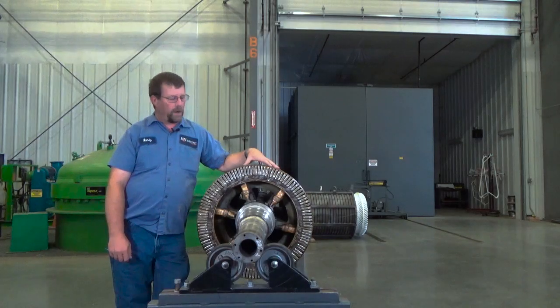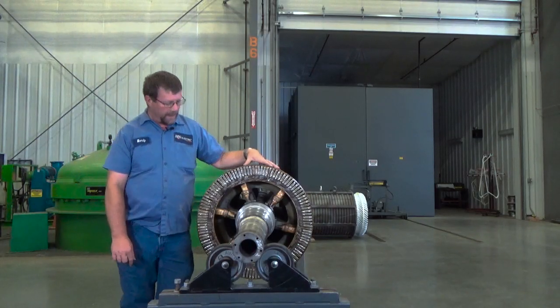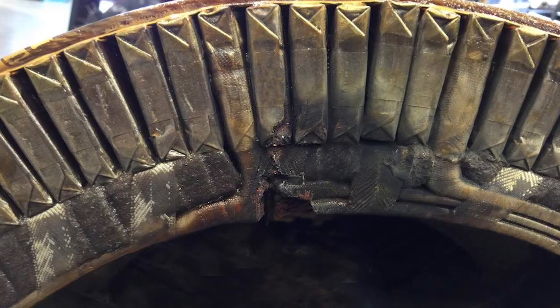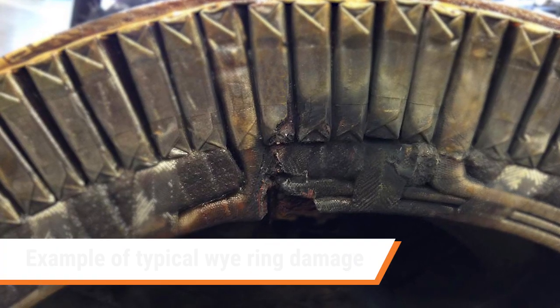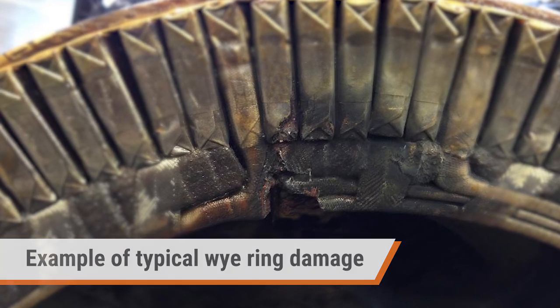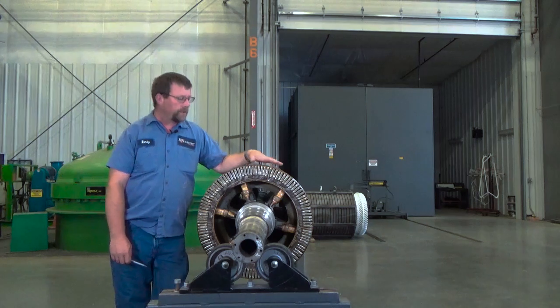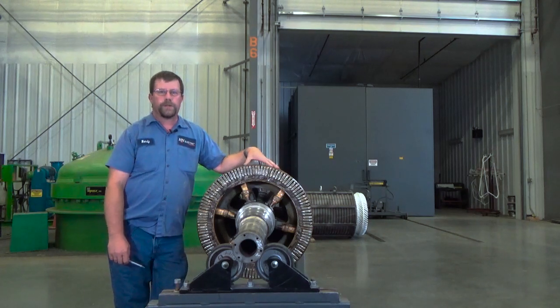Now I'd like to talk to you about wye ring damage. This wye ring is obviously catastrophic damage. The wye ring has failed, it has damaged the insulation on the coil packs behind the connection and has gone to ground. So this rotor now is an expensive rewind.